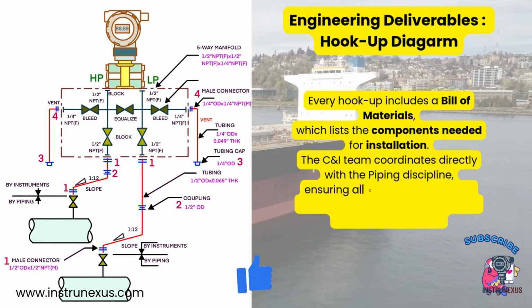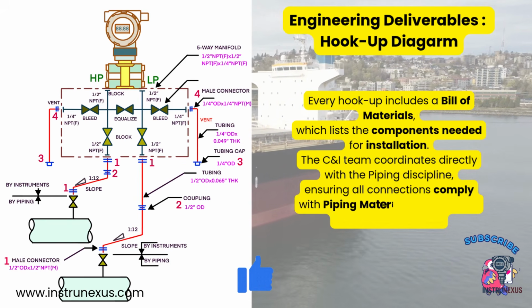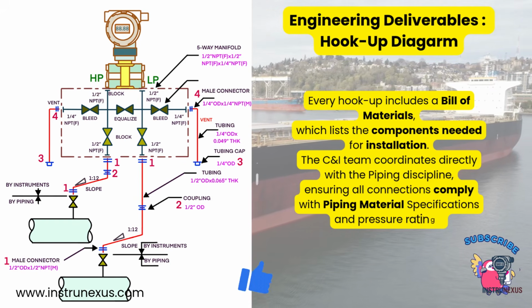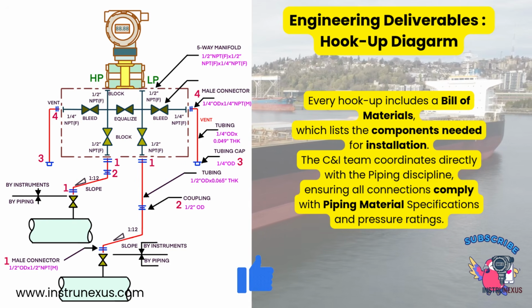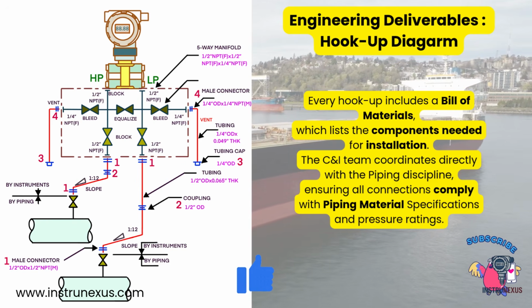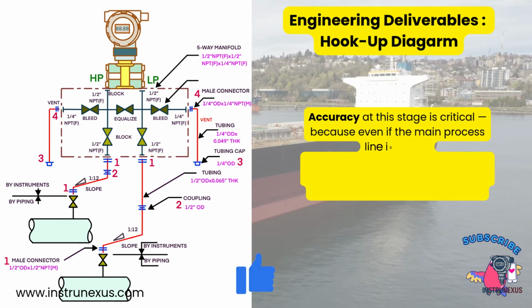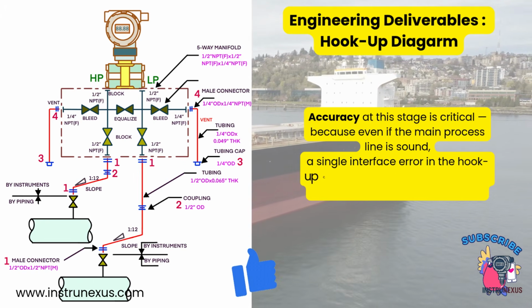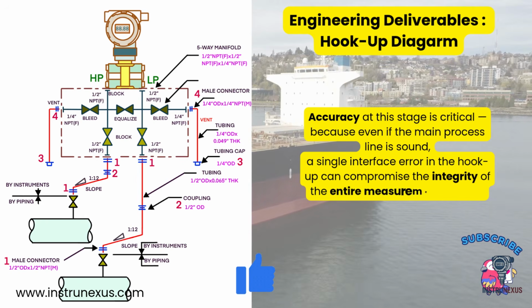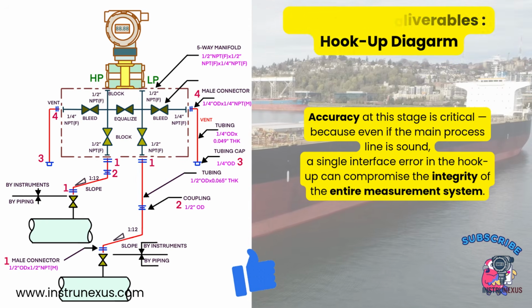The C&I team uses these drawings to communicate directly with the piping discipline, ensuring that all small bore connections comply with the piping material specification and the required pressure rating. Accuracy here is critical, because even if the main process line is robust, a single error in the hookup can compromise the entire instrument interface.